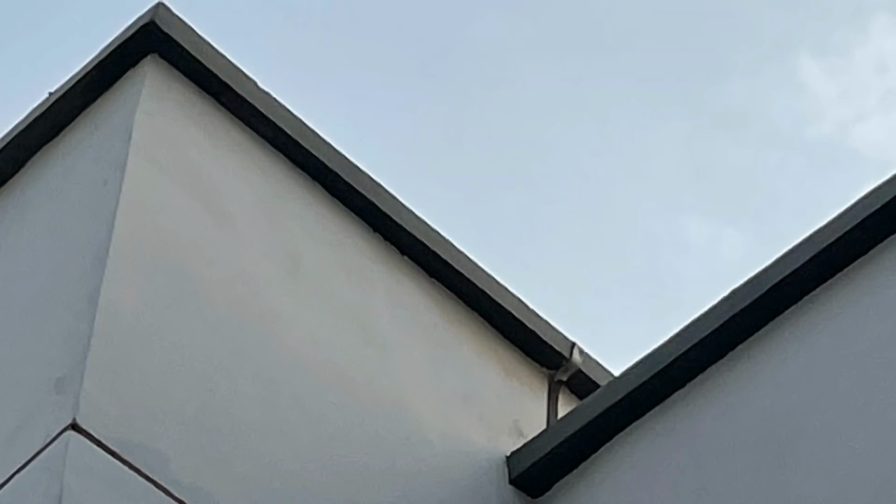You can see the air spike or air termination rod, and you can see copper tapes running along the roof. Those two items form what we call the air termination network. Now, the copper tapes that run on the roof are generally 25 millimeters wide by 3 millimeters high.